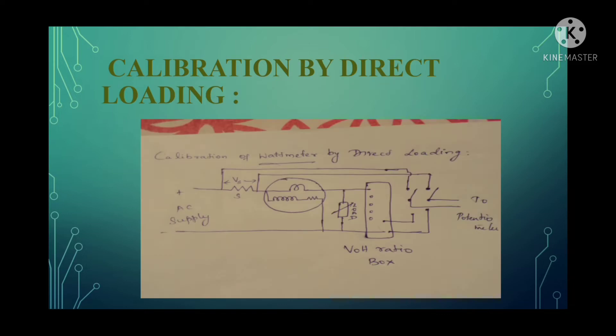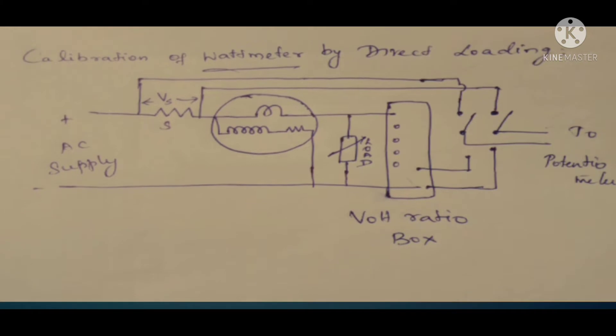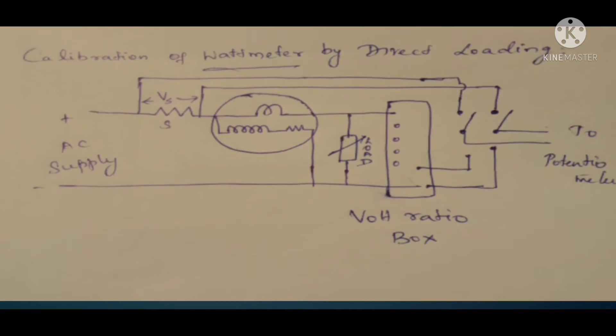First we shall see about the direct loading method of calibration of wattmeter. This is the circuit arrangement for calibrating a wattmeter using the direct loading method, where we connect a load across the wattmeter based on the power rating of the wattmeter. A variable load is connected here, and this variable load carries the current, consuming some amount of the supply provided. By means of connecting a standard resistor, the current entering the circuit is measured using a potentiometer, and the voltage drop across this load is also measured using a potentiometer arrangement.